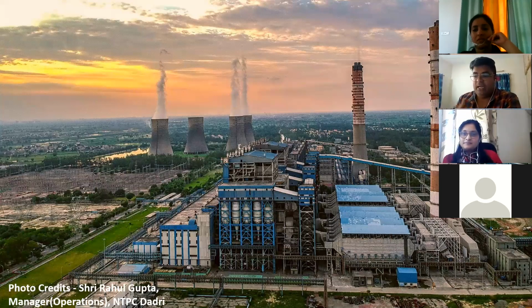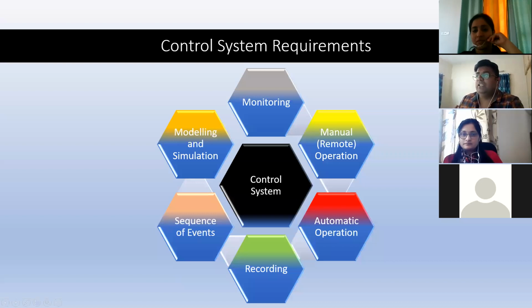There are preventive maintenance schedules for each power plant, and as we were talking, the control system requirement actually helps you in monitoring and recording. These two actions done by the control system help you in doing the preventive maintenance. The monitoring and recording give you the data to analyze how to slot your preventive maintenance for each system. Some systems may require monthly maintenance, some may require 6-month maintenance, some may require every day, like filters that need to be cleaned every fortnight or every week for a particular system.